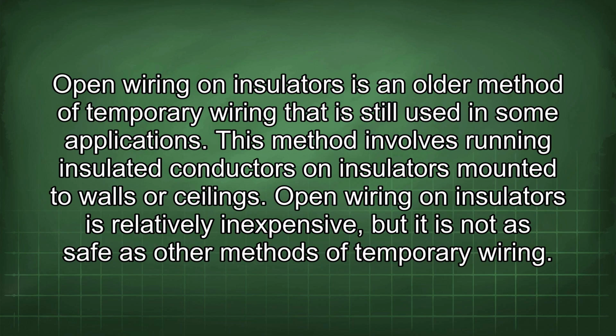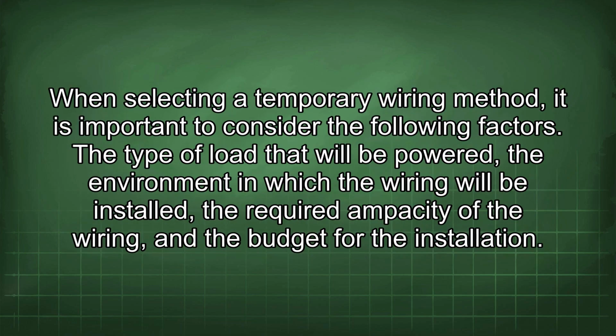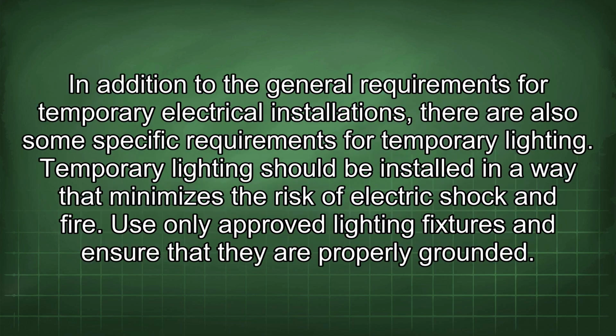Open wiring on insulators is an older method of temporary wiring that is still used in some applications. This method involves running insulated conductors on insulators mounted to walls or ceilings. Open wiring on insulators is relatively inexpensive, but it is not as safe as other methods of temporary wiring. When selecting a temporary wiring method, it is important to consider the following factors: the type of load that will be powered, the environment in which the wiring will be installed, the required ampacity of the wiring, and the budget for the installation.